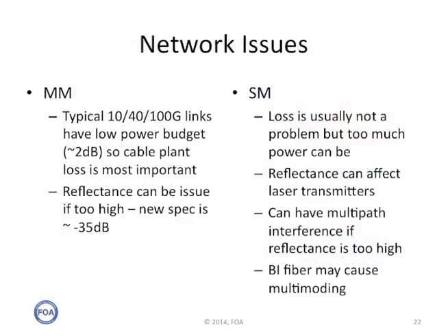Single mode and multi-mode fibers have different problems when used in data centers. Multi-mode links have bandwidth distance limitations due to modal dispersion. The derating factors for dispersion on multi-mode fiber can limit power budgets to as low as 2 dB, not the 5 to 6 dB you would figure from looking at the transmitter output and receiver input levels. Single mode links are capable of longer runs, so loss is not an issue, unless the loss is too low and attenuators are needed at the single mode receivers because of overloading.